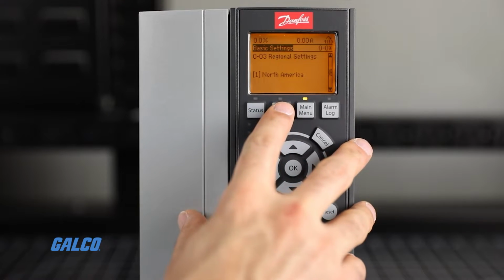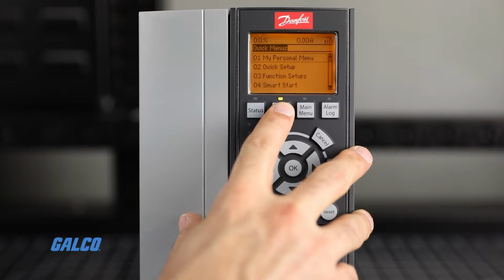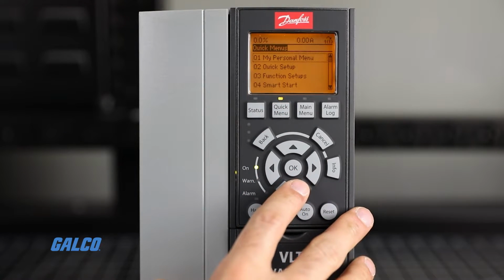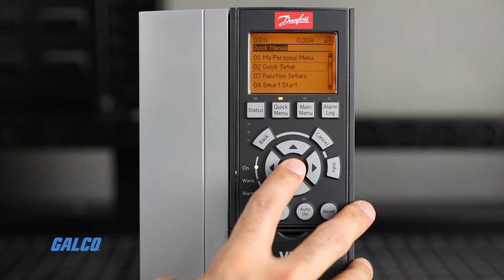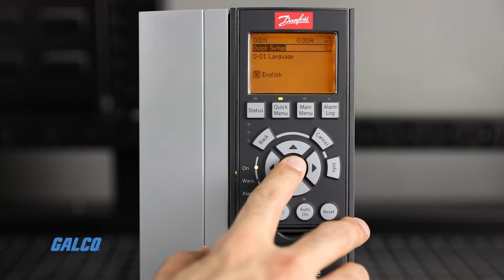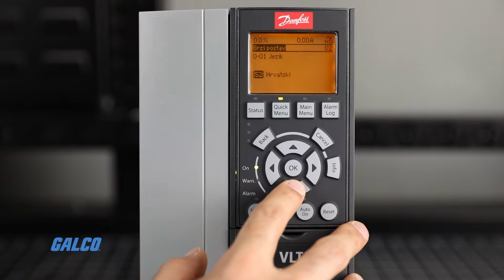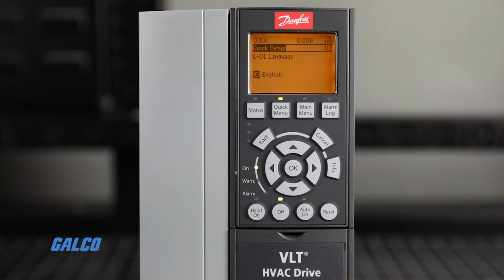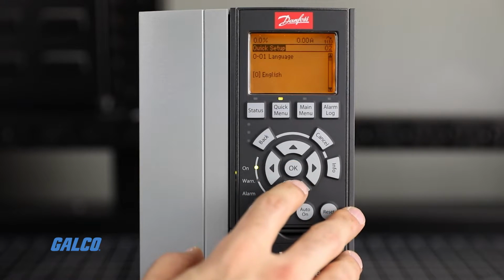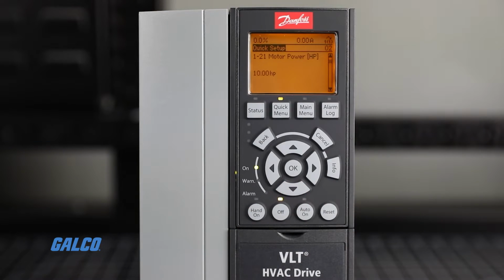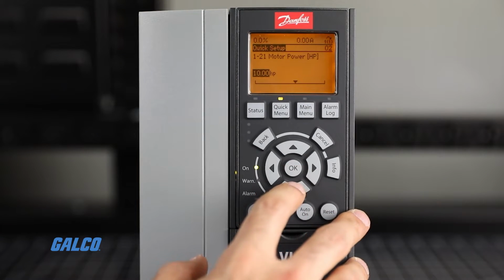Next, hit the Quick Menu key and enter Q2 Quick Setup. The Quick Setup group takes you through a limited set of parameters that are necessary for operation. These parameters make it possible to program for most HVAC applications. Use the arrow keys to move through the parameters in this group. First, confirm your language. Next, enter your motor power at parameter 1-21.